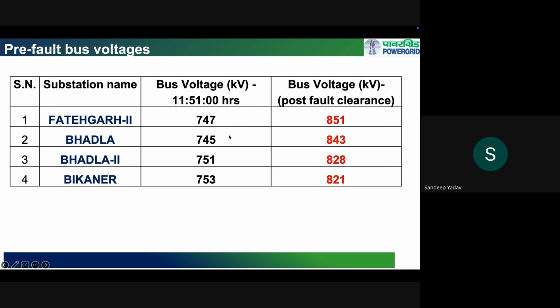You can see the lack of system strength, because of the lower number of synchronous machines connected in the Rajasthan area. What is happening is that the pre-fault voltage is in the range of 740 kV at almost all substations, and there is a rise in voltage after fault recovery. So when the fault is gone, or the faulty line has been isolated, the change in voltage is significantly higher. From 747 it becomes 851, 745 to 843. At Bhadla 2, from 751 to 828.